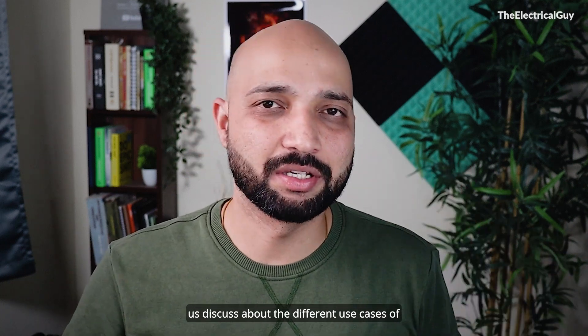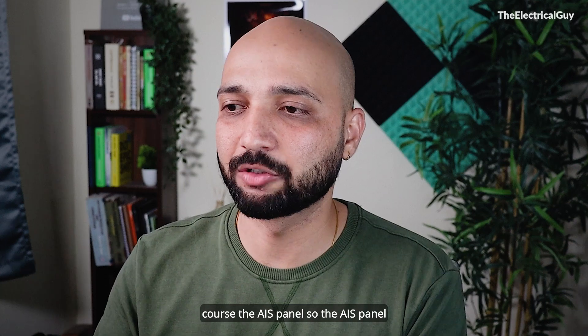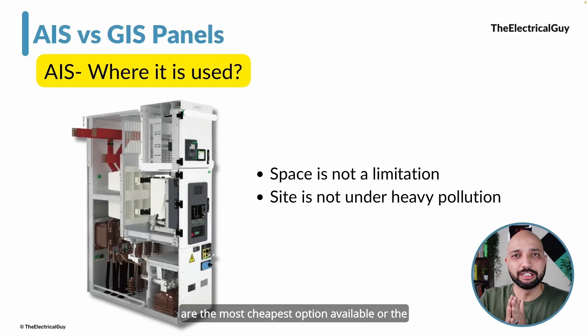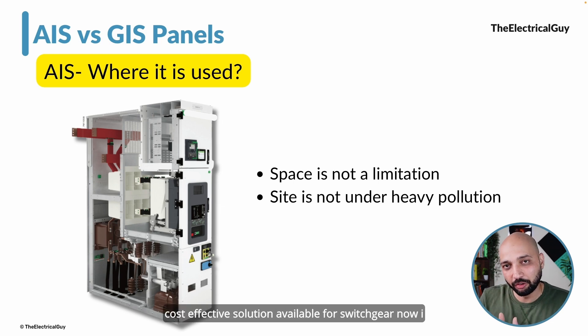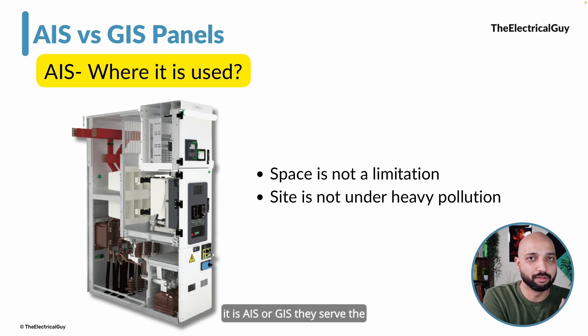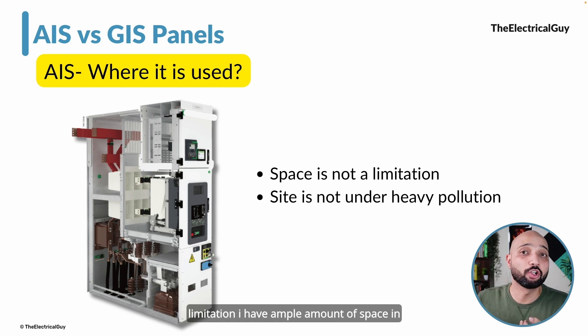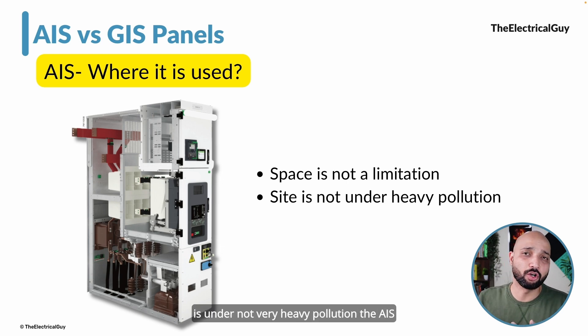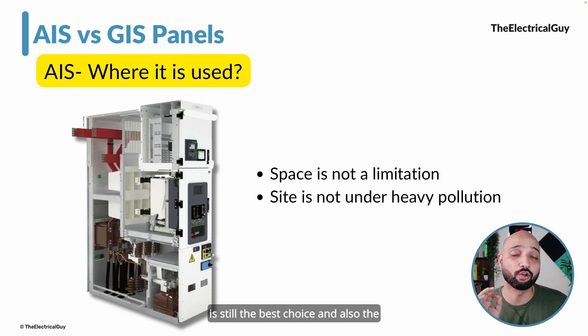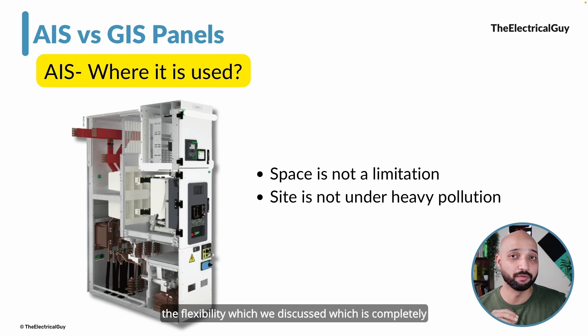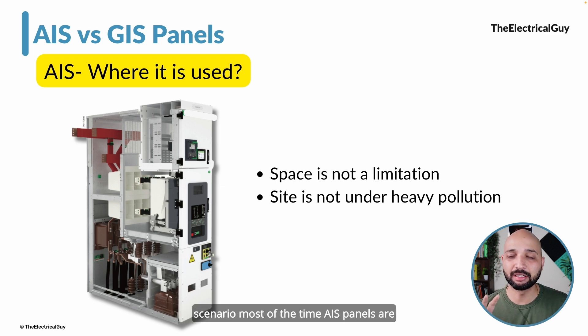Now let us discuss different use cases. AIS panels are the most cost-effective switchgear solution. Both AIS and GIS serve the same purpose — the difference lies in the technology used. Where space is not a limitation and the site is not under very heavy pollution, AIS is still the best and most cost-effective choice. It also offers flexibility — such as withdrawable components — which is absent in GIS. In such scenarios, AIS panels are mostly preferred.